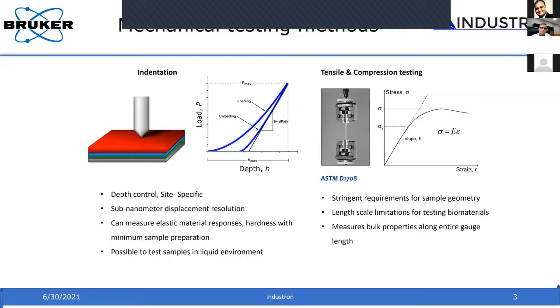so how do we apply this force? We need to generate force. Sometimes, for example in air, you can have a spring, and the deflection of the spring can be measured as force. But when you need higher forces, you need to generate the force. The way we generate it with our instrumentation is through electrostatic force actuation. We have a capacitive sensor, which has a three-plate capacitance structure, and the center plate is suspended by a spring.